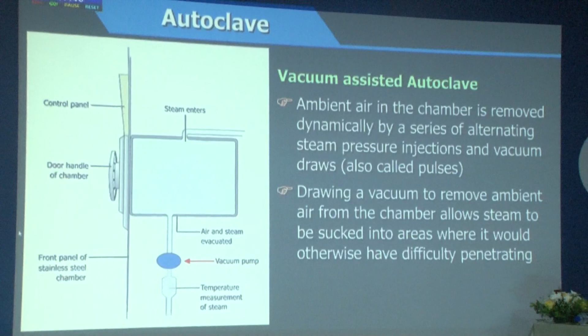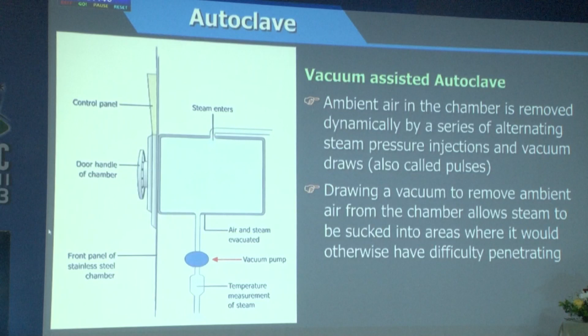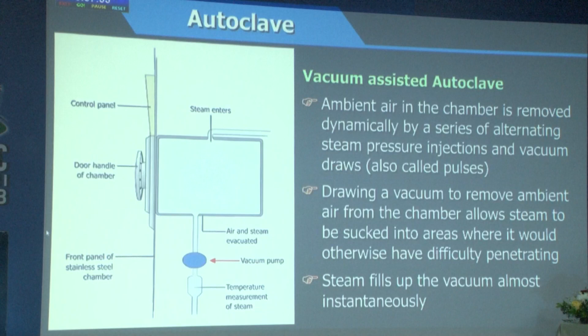So you just add on a vacuum pump to your traditional autoclave where you have the pre-vacuum and the post-vacuum cycle. This is able to remove the air inside the autoclave, create a perfect vacuum, and hence the steam is able to penetrate all the areas and have an adequate sterilization process. When you have multiple cycles of the steam and vacuum, it is simply called the Class B autoclave. A single cycle is called the Class N autoclave. It's quicker, keeps the load dry. The most disadvantage is it's expensive.